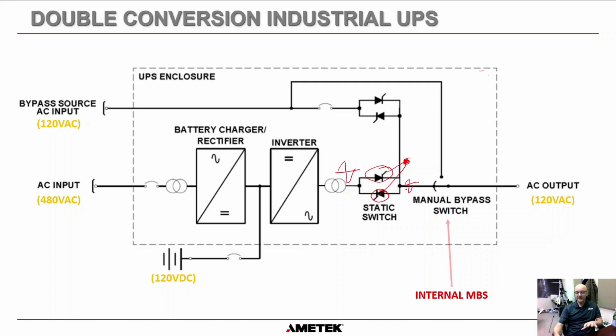So static, as in no moving parts. It is completely semiconductor and electronic driven for a static switch, and for a manual bypass switch or maintenance bypass switch, it is nearly always a mechanical switch that has moving parts. Okay.